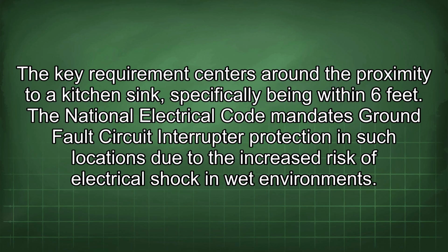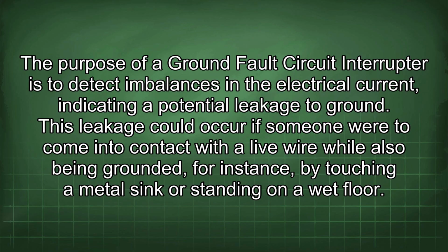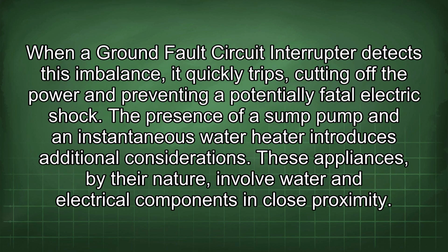The key requirement centers around the proximity to a kitchen sink, specifically being within 6 feet. The National Electrical Code mandates ground fault circuit interrupter protection in such locations due to the increased risk of electrical shock in wet environments. The purpose of a ground fault circuit interrupter is to detect imbalances in the electrical current, indicating a potential leakage to ground. This leakage could occur if someone were to come into contact with a live wire while also being grounded, for instance, by touching a metal sink or standing on a wet floor. When a ground fault circuit interrupter detects this imbalance, it quickly trips, cutting off the power and preventing a potentially fatal electric shock.